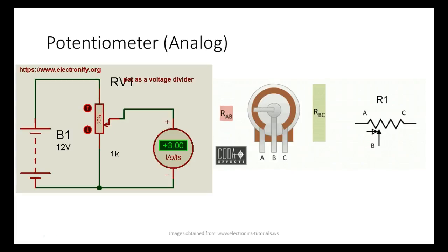Determine the position. So if we had 10 volts and I can move it 6 inches maximum, I could take 6 divided by 10, and that would get, I'm sorry, I'd take 10 and divide it by 6, and that would give me what we call our volts per inch. Does that make sense? Now over here we have two of them.